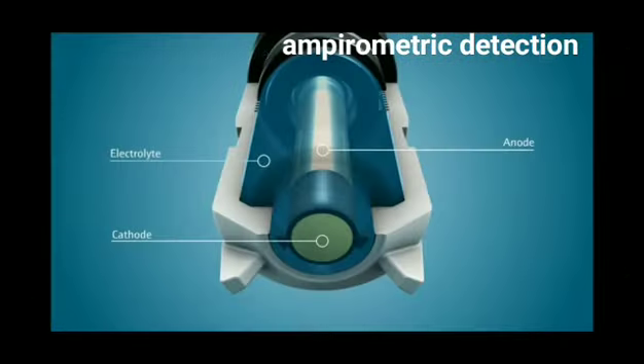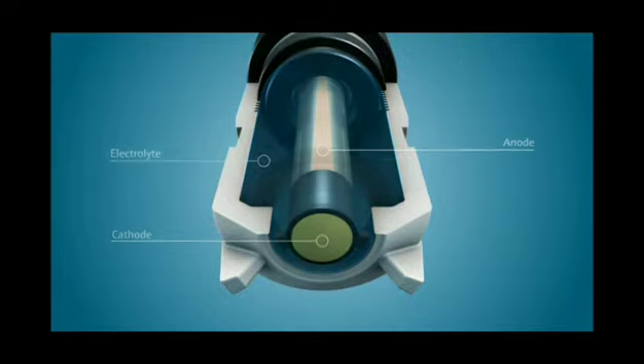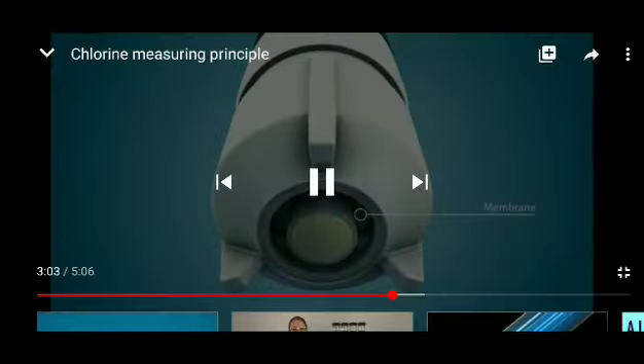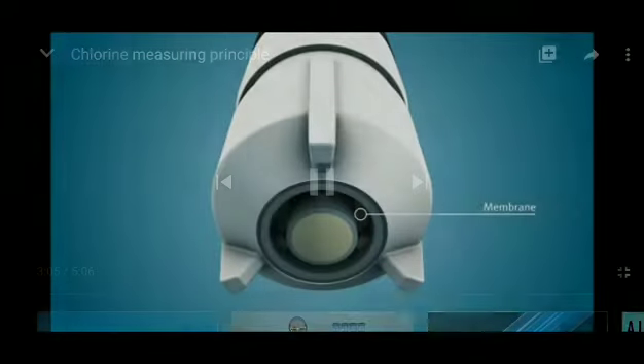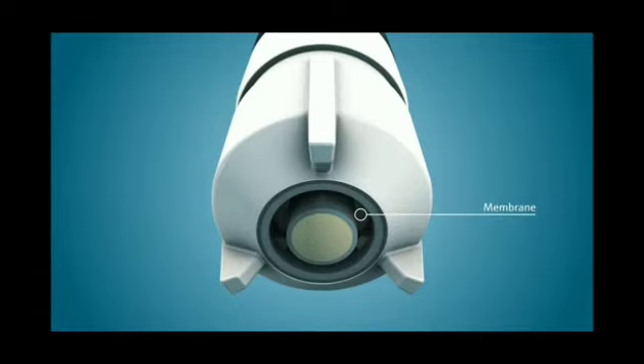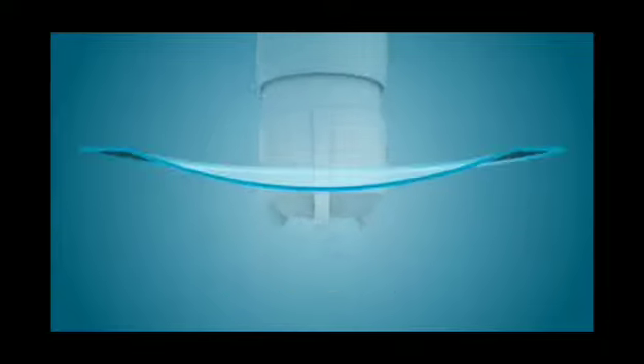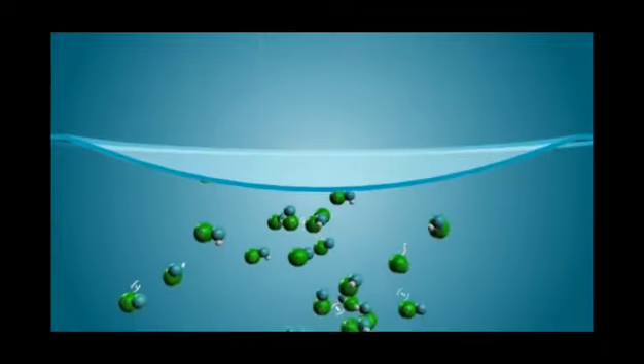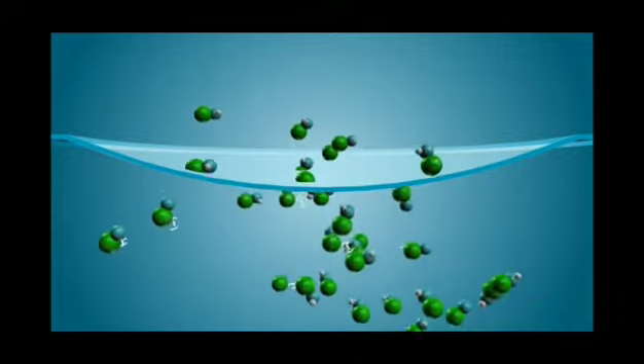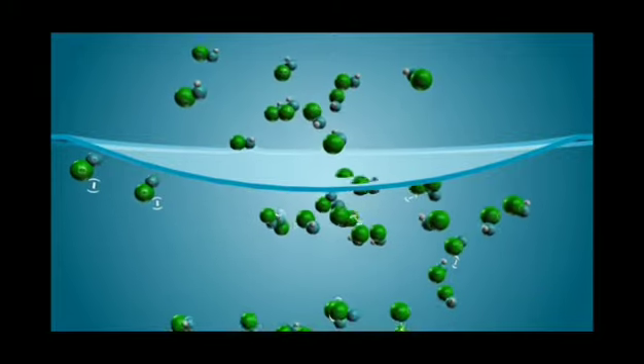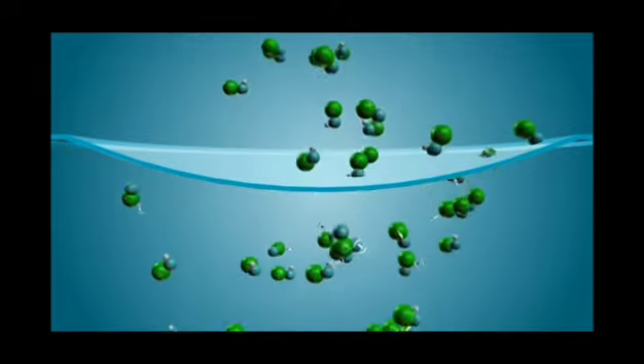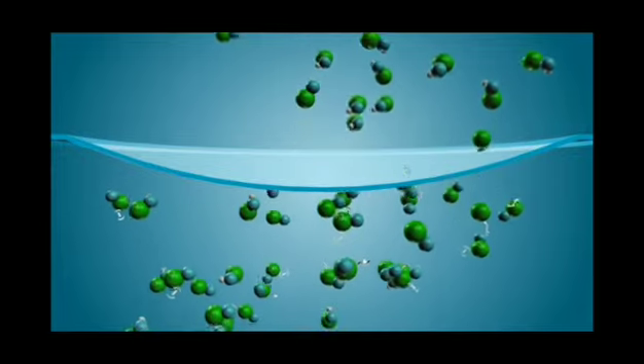The reaction chamber is filled with an electrolyte. A membrane separates the reaction chamber from the medium to be measured. The membrane is made of superhydrophobic PVDF. It allows gaseous HOCl molecules to diffuse while it repels OCl ions due to their negative charge. The membrane shows a behavior similar to cell membranes of bacteria, for example.